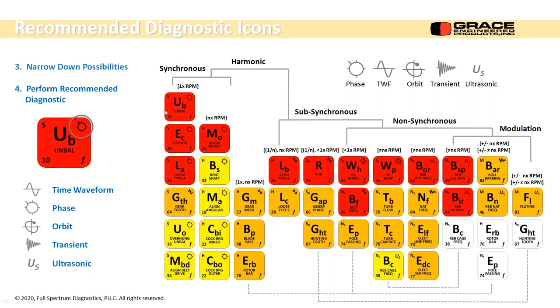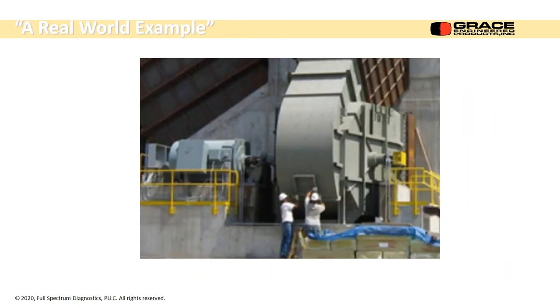This is telling us what to do. So I've sorted by frequency content, I've sorted by direction, and then I go and do my diagnostic test to narrow it down, hopefully to the root cause. All right, so this is a lot of stuff, but without a demonstration, it's not as acceptable. So we got one more little twist on this. I got a real world example here. We have an AC induction motor. It's direct coupled. We have a center hung fan, inner and outer bearings. They're rolling elements in this case. So everything's set up. What else do I have? It's an AC motor, so it's not DC. Okay.